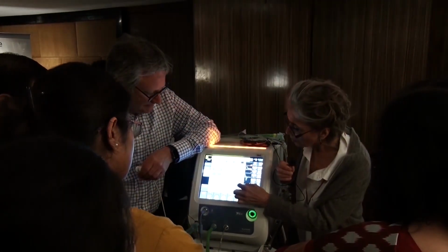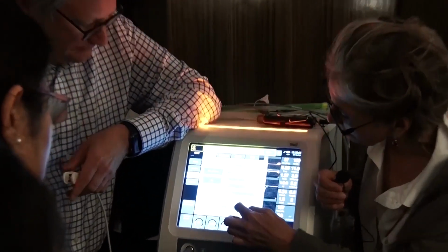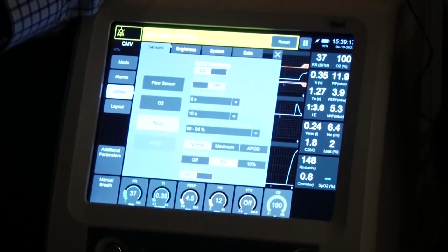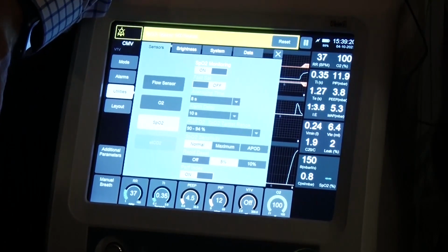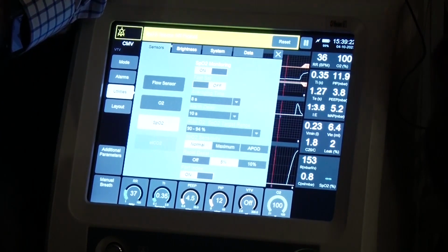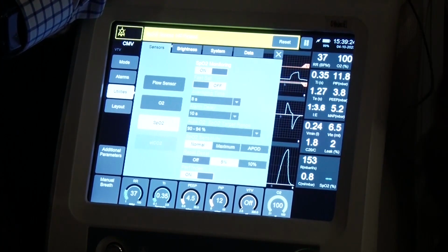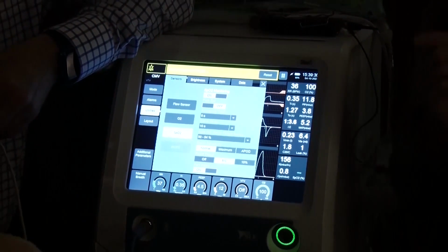If you're not comfortable with that, I'll just give this one. So here is to remove the delay of the audible alarms. It means that here, for example, you set a low target at 90, your low alarm of the SpO2 is at 90. If it drops 5 below, at 85, immediately you will have the alarms. It doesn't give you any delay. So like that, you know what is happening in your patient, and you avoid some alarms.